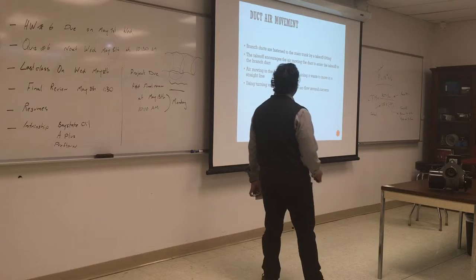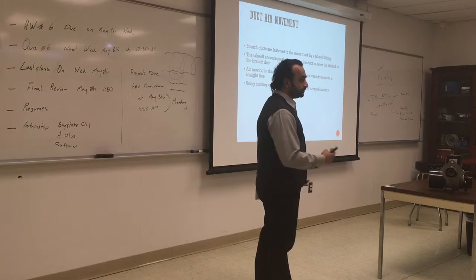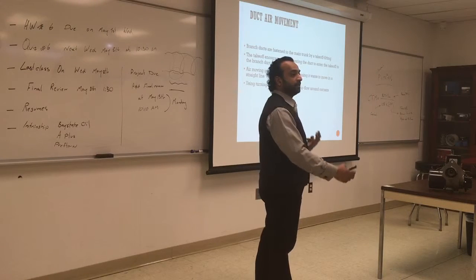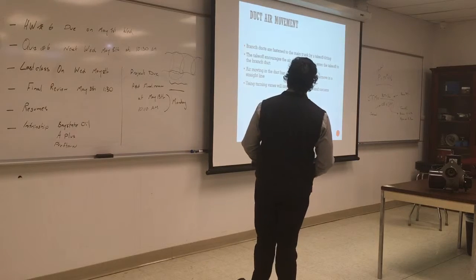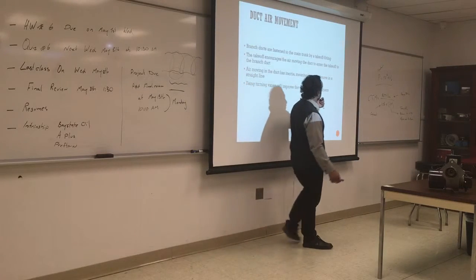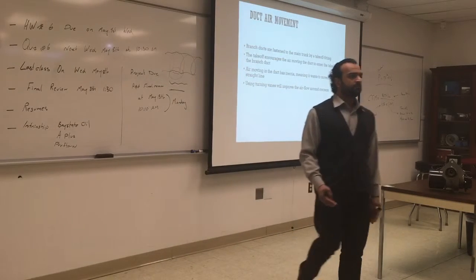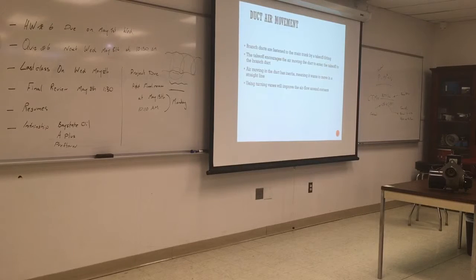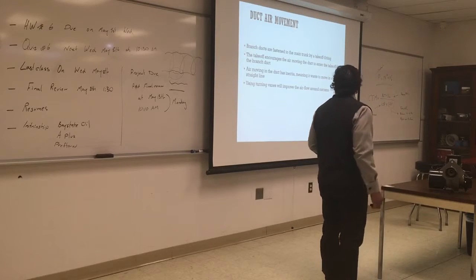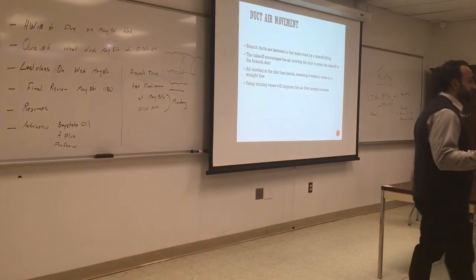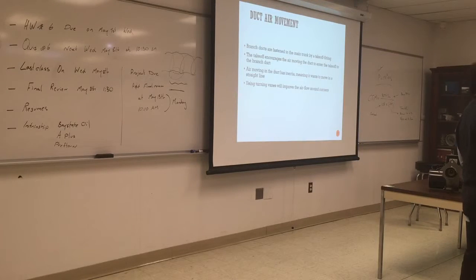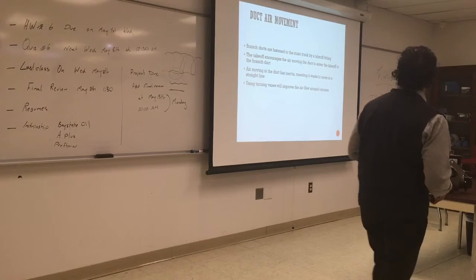Air movement in duct has inertia, meaning it wants to move in a straight line. So if you give it a lot of resistance, it will swirl and create a lot of vortices, and that will slow down the air from moving. Turning vanes will improve the airflow around corners. So what are turning vanes? Kind of like a fitting for the pipe, 45 degrees, 90 degrees. You want to stick with around 45 or 90, and those will smooth out the turn. It's a fitting also with some kind of streams in it, so the air does not have a lot of friction and does not swirl a lot, and you do not encounter a shock wave when the air goes too fast and you have a big vortex inside that shocks your flow.